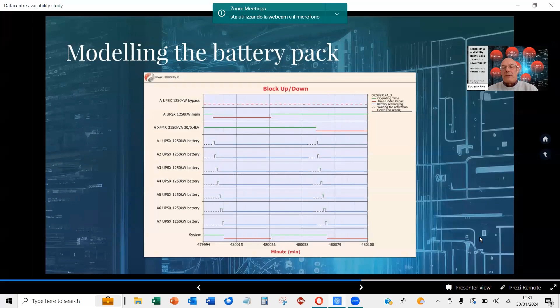Diesel generator. The data center is equipped with a number of diesel generators to provide alternative power to the load, and the generators are expected to take approximately 40 seconds to reach nominal speed and to operate for another 30 minutes after being cleared. So we were given this number to take into account in our design. So we had to make sure that the generator will come on after 40 seconds, 45 seconds, and they will stay on for another 30 minutes.